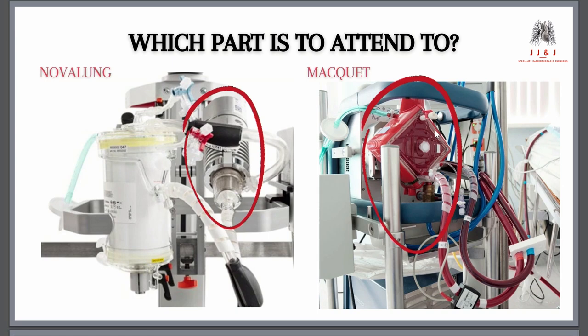On the Nova Lung machine, the oxygenator and the centrifugal pump are two separate components — the centrifugal pump is the smaller one connected to the machine, and the oxygenator is the cylinder. With the Maquet, it's all in one system. In the case of the Nova Lung, you would go to the centrifugal pump to fix the problem, not the oxygenator.